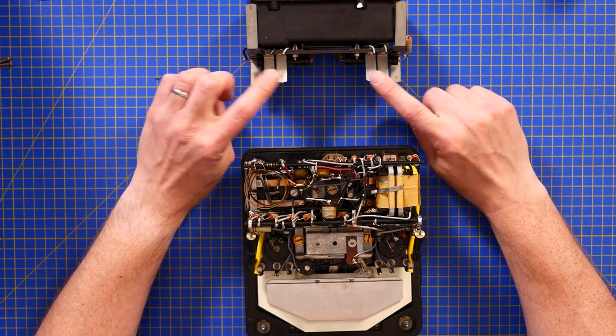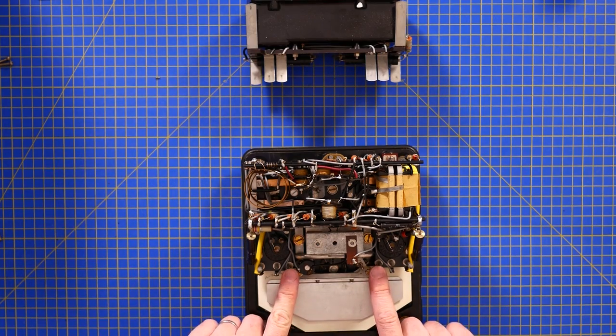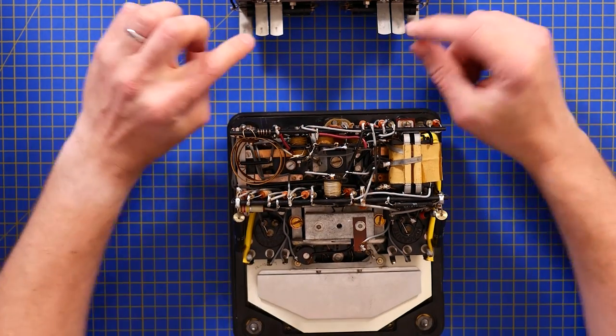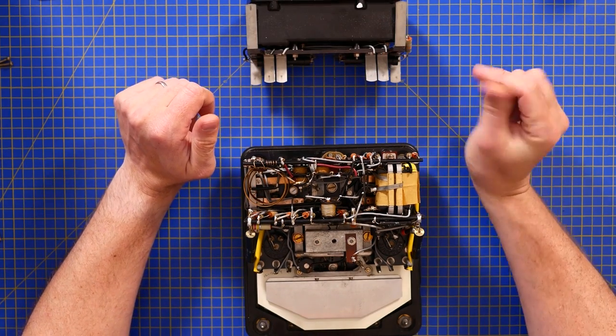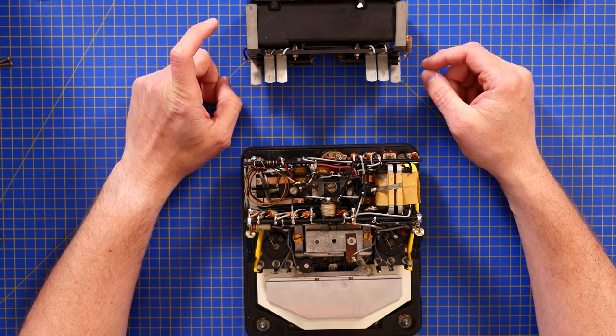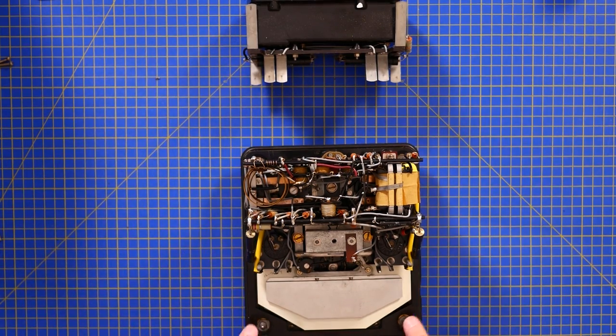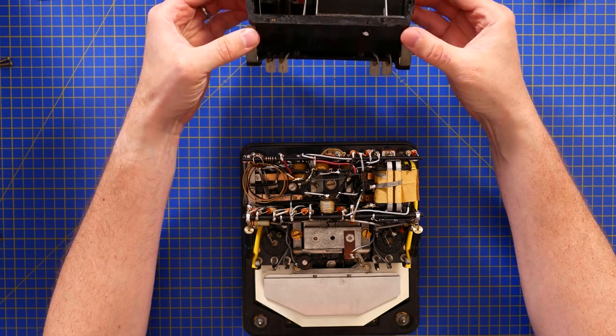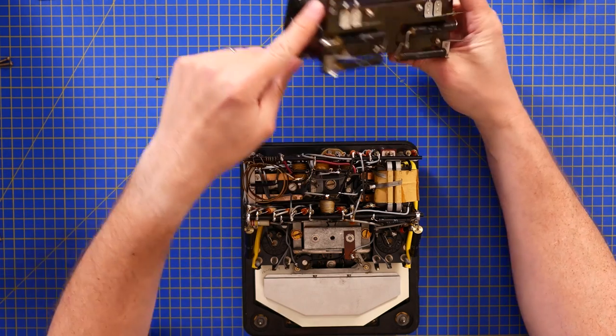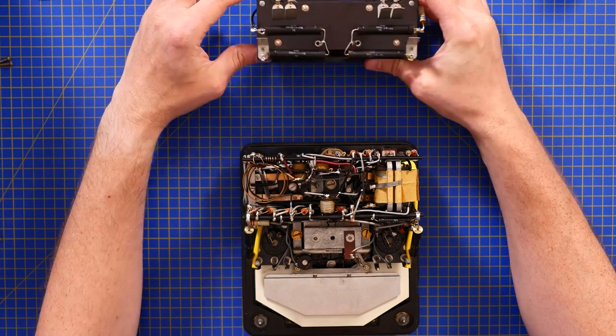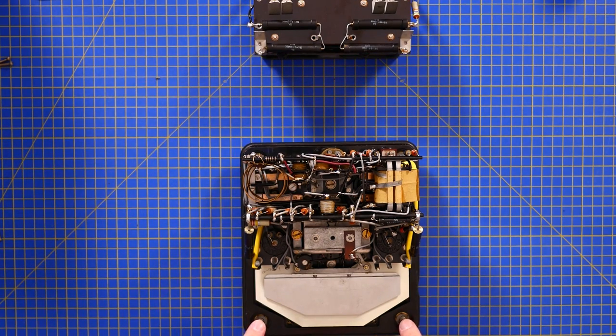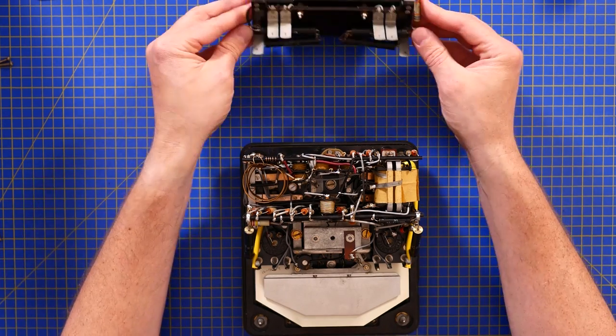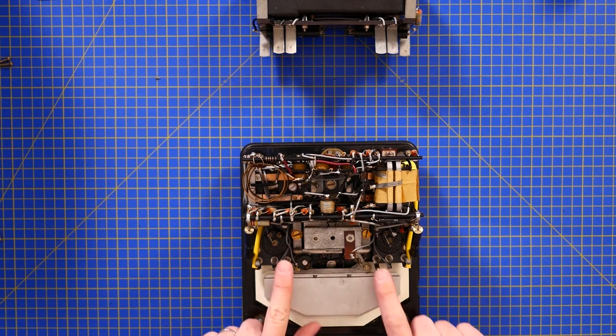These six terminals from the battery compartment actually lined up with these six pins here. And they are large pointy sticks just to transfer power effectively. I wouldn't have thought you'd want that fine point of contact, but I guess it's a very small current you're drawing from the batteries at any one time. What is also interesting is these two pins up here which are used for measurement. They press on these two from the battery box. They're actually the connectors which go through these big resistors. So all you're doing is taking from here, running through big banks of resistors onto these two longer prongs for certain measurements. Then you've got the 15 volts and 1.5 volts going to the shorter stakes.